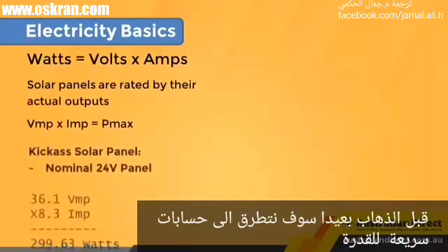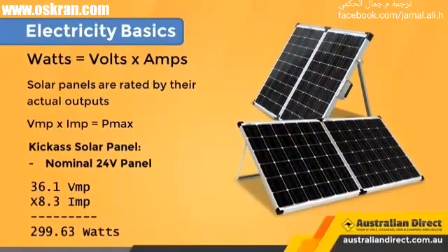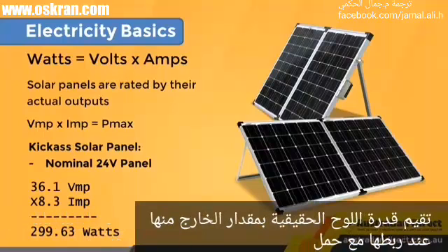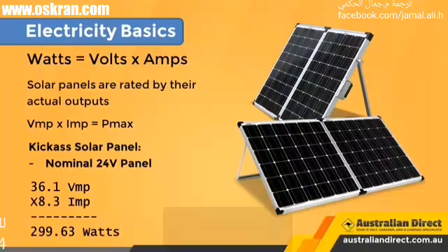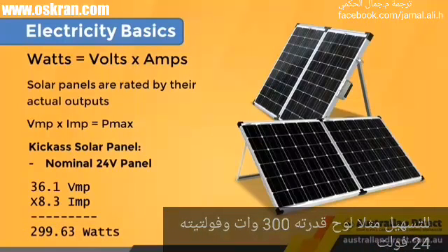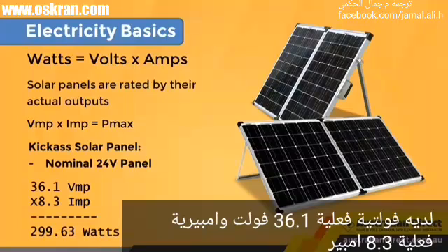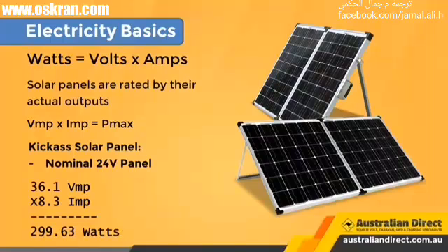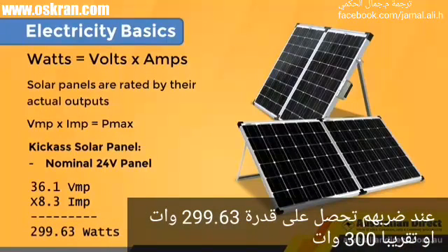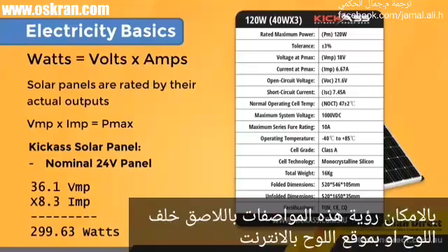Before I go further, I want to go over a quick reminder of power calculations. Solar panels are rated by their actual output when connected to a load. For instance, a generic 300-watt 24-volt nominal panel has an actual output of 36.1 volts VMP and 8.3 amps IMP. When you multiply them together, you get the rated watts — 299.63 watts, rounded up to 300 watts. You can see the specs on the solar module's back or in its datasheet.